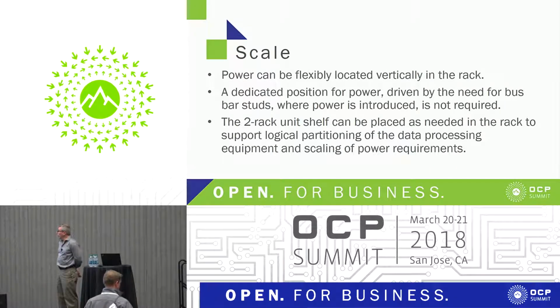In terms of scale, it can be mounted anywhere in the rack. You can add rectifiers. You don't have to put in all four rectifiers if you don't need the full 24 kilowatts. Don't have to pay for that up front. If you subsequently find you need more, you just plug in more rectifiers. And as I say, they're plug and play. If you have a failed rectifier, it will get reported. You can unplug the failed one, identified by the lights. Typically in the telecom world, red is a failure and green is good, and that's typically the way our rectifiers work. Although we're obviously looking at the Facebook specification using blue indicators for colorblind recognition.